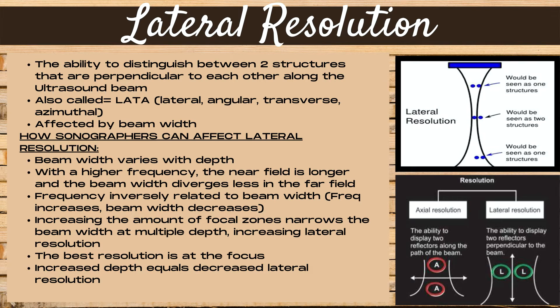Frequency is inversely related to beam width — as frequency increases, beam width decreases. Increasing the number of focal zones narrows the beam width at multiple depths, which increases lateral resolution, and the best resolution is at the focus. Moving the focal zone to be at or slightly below the area of interest decreases beam width and improves lateral resolution. Increasing depth decreases lateral resolution.